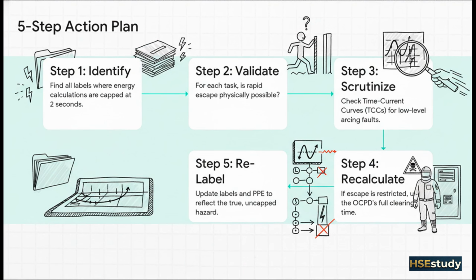And here's your 5-step action plan. Step 1. Pull your studies and find every single label where the incident energy was capped at 2 seconds. And you might have to dig for it. It's often a buried setting in the software. Step 2. For every single one of those tasks, validate the assumption. Is escape really possible? Be brutally honest.